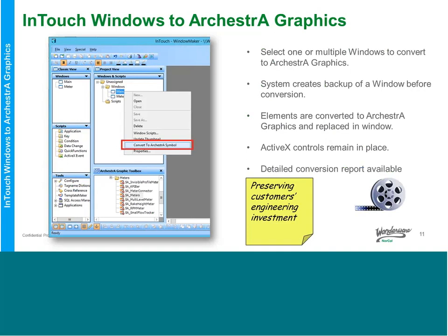You can convert existing InTouch windows to ArchestrA Graphics. So just to be clear here, this doesn't actually change the graphics, the way they look, meaning it's not going to take an old graphic and convert it to a new style graphic, but what it's going to do is change the InTouch window to a vector-based window that can be edited inside of the ArchestrA symbol editor.